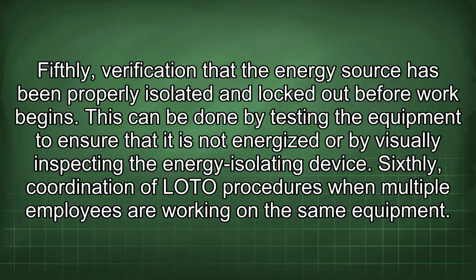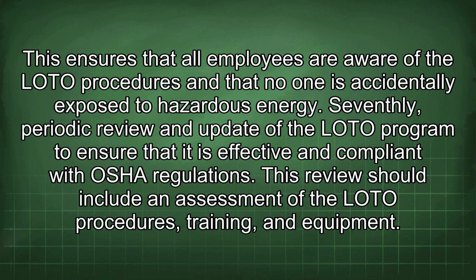This can be done by testing the equipment to ensure that it is not energized or by visually inspecting the energy isolating device. Sixthly, coordination of LOTO procedures when multiple employees are working on the same equipment. This ensures that all employees are aware of the LOTO procedures and that no one is accidentally exposed to hazardous energy. Seventhly, periodic review and update of the LOTO program to ensure that it is effective and compliant with OSHA regulations. This review should include an assessment of the LOTO procedures, training, and equipment.